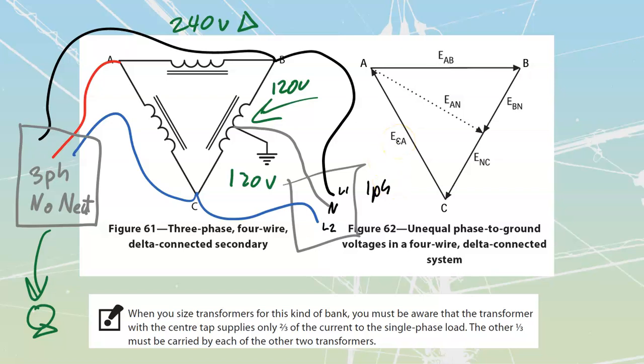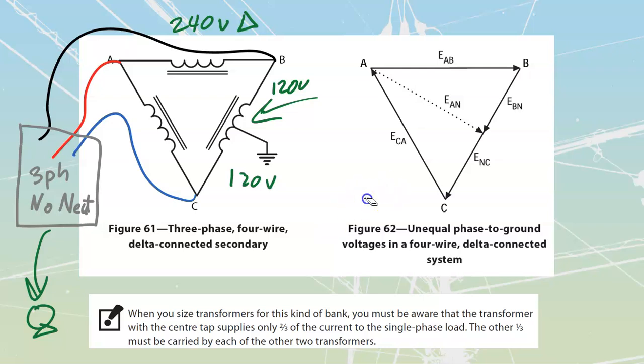You're never allowed to combine all of these together into the exact same panel. Having a 3-phase panel with a neutral inside of it is allowable. It's doable on a 120/208 volt system, but not on one of these systems, because of what could accidentally happen.